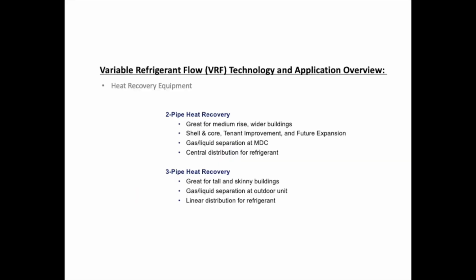We also get asked, where would we use 2-pipe and where would we use 3-pipe? They're both heat recovery. They both do the same thing, but where would you use one versus the other? And I would say we would typically use a 2-pipe heat recovery system in a large, wide, open building, typically like 1 to 2 floors, where you can mount the multi-port distribution controller in a central location, since these are usually larger, anywhere from 8 up to 12 ports. So we would mount those in a central location, and then it would be easier to route the refrigerant piping from each zone back to the multi-port distribution controller.